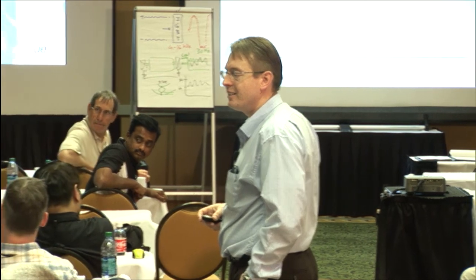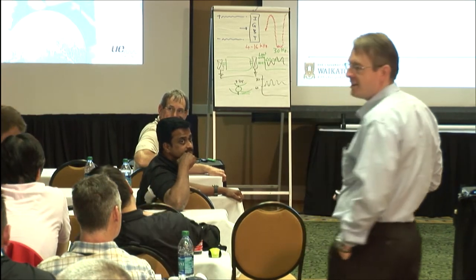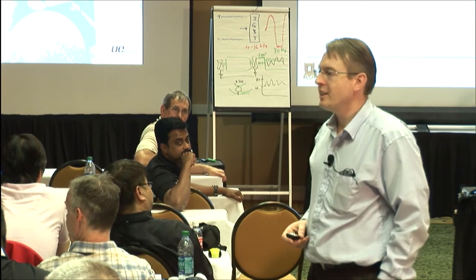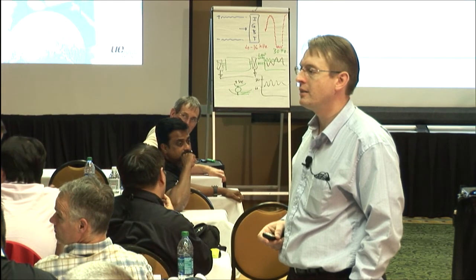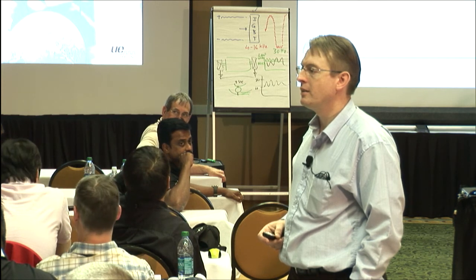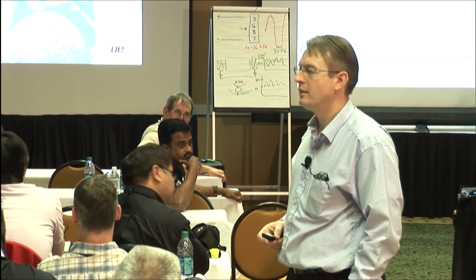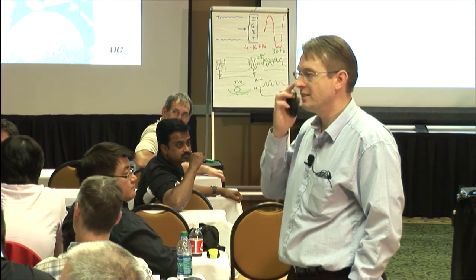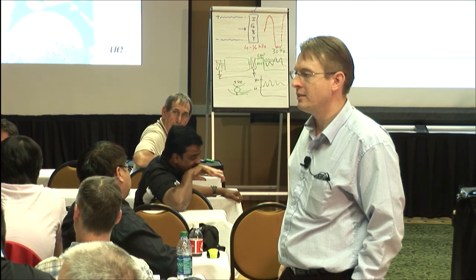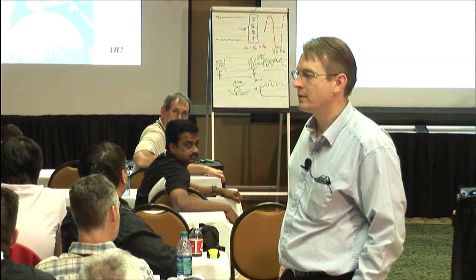Hey, James, we've got a lot of people that are looking at replacing their air compressors. They've got a modulating compressor sitting in now. Companies are coming in and doing their compressed air audits, and they're recommending that they take out a 100-horse, or maybe even two 100-horse modulating compressors, replacing one with a variable speed drive compressor that's probably 100-horse, which maybe would carry the whole load. So what you're saying is, instead of going that complete replacement, it'd almost be better to stay with what they have, running 80 to 100% loaded, rather than go to the variable speed drive.